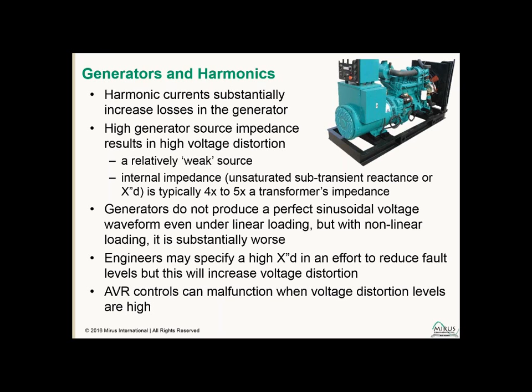And as we get into high voltage distortions, we get AVR control issues or excitation control issues. AVRs do their voltage sensing either to respond quickly to a true RMS value or to a fundamental frequency component. They cannot, or should not, respond to any harmonic distortion. So if the distortion levels get high and the AVR does respond to that, it can cause instability issues. And excitation controls will usually take their power from the output of the generator, and if it's badly distorted, it can cause excitation control issues. So certainly the recommendation to oversize to minimize these problems associated with nonlinear load is required when we have these harmonic generating loads.